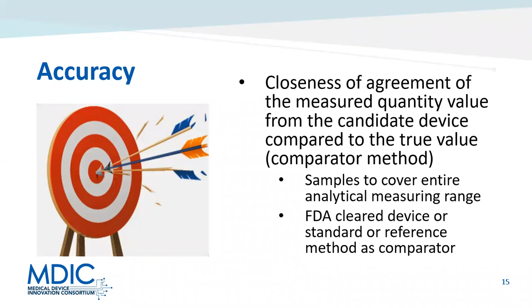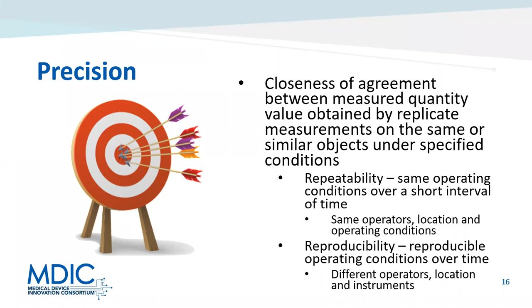For precision testing, the same sample is tested multiple times under specific conditions. Precision testing includes both repeatability, which is completed over a short period of time with the same operating conditions, and reproducibility, which can be over a longer period of time and includes different operating conditions, including the location, devices, and operators. Sample stability should be taken into account when planning your precision studies, as well as the medical decision levels for quantitative assays, as it's important to characterize the precision at those particular levels as different decisions are being made based on those results. We go to the next slide.